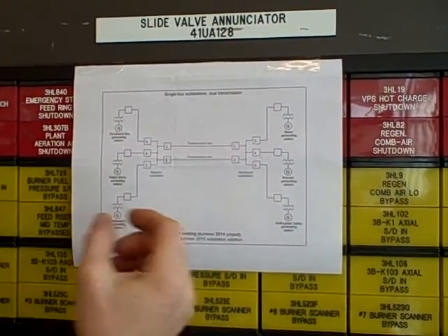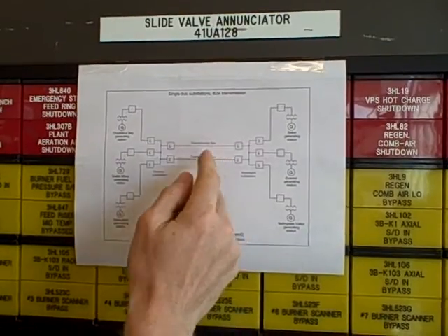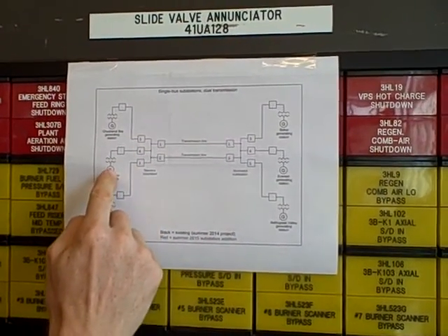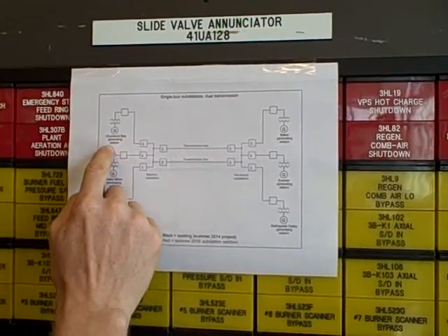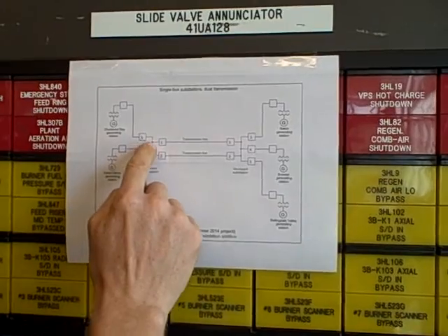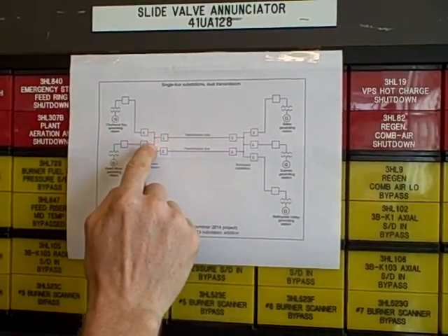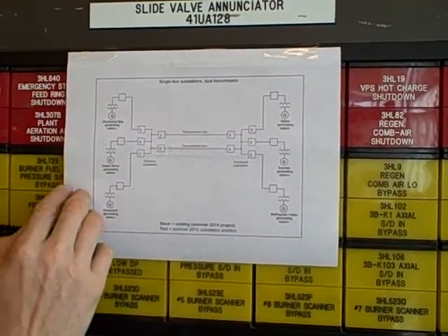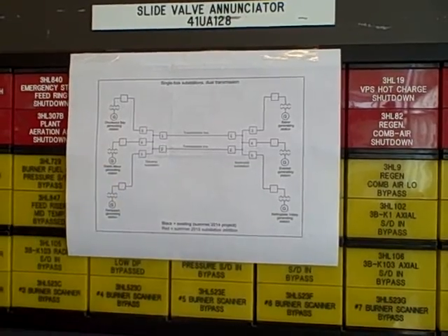That's going to be a direct phase-to-phase fault on the line that will draw a large amount of current from the generator. All that current will pass through the Stevens substation and back as it returns, and that's going to load down the generator.